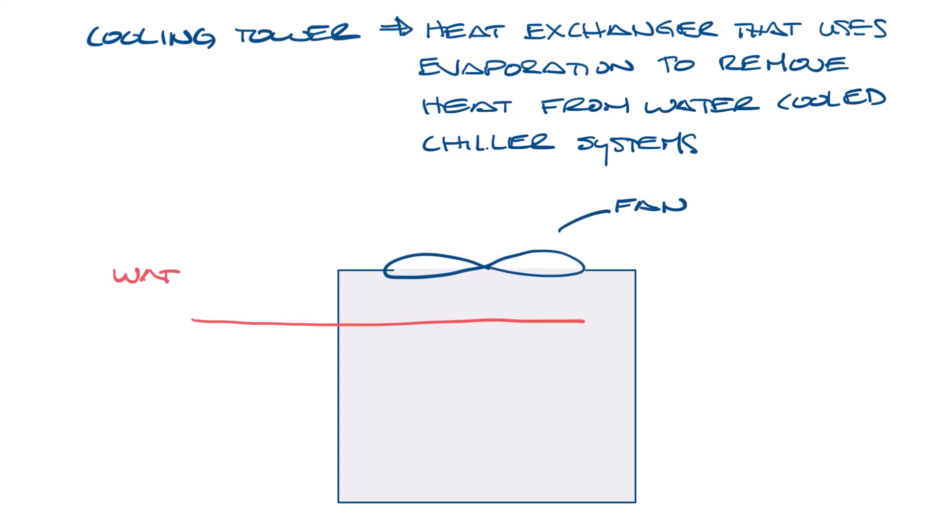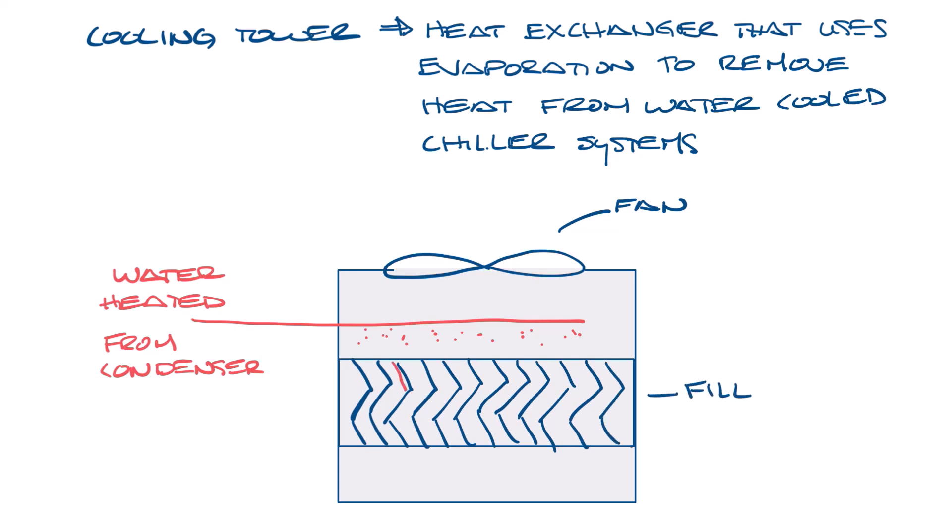Water which has been heated by the condenser is pumped into the cooling tower and distributed onto banks of media called fill. Water from above will run down the fill kind of like this, slowing the flow of water through the cooling tower and exposing it as much as possible for maximum air to water contact.